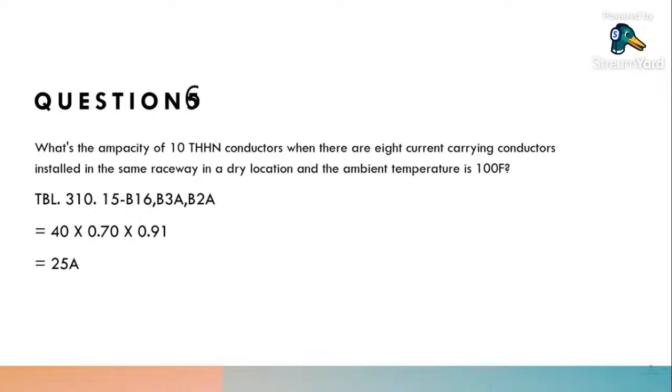All right, so the next question I'm going to look at here is the ampacity. What's the ampacity of a 10 THHN conductor when there are 8 current carrying conductors installed in the same raceway in a dry location and the ambient temperature is 100 degrees Fahrenheit?